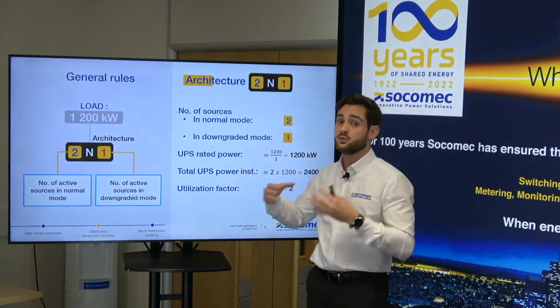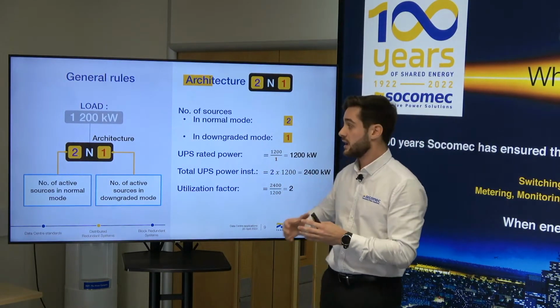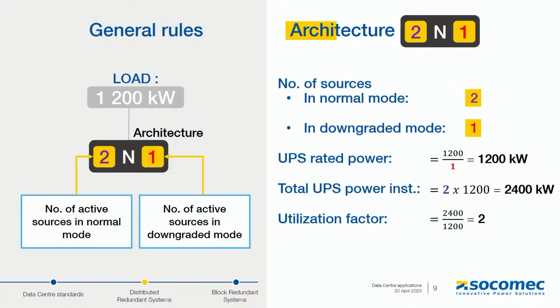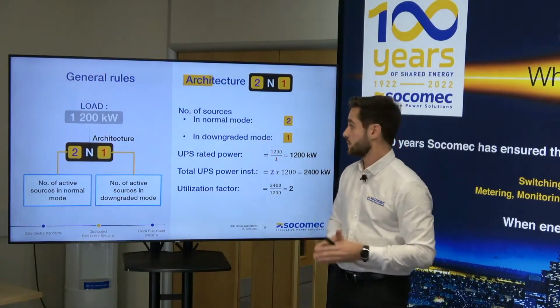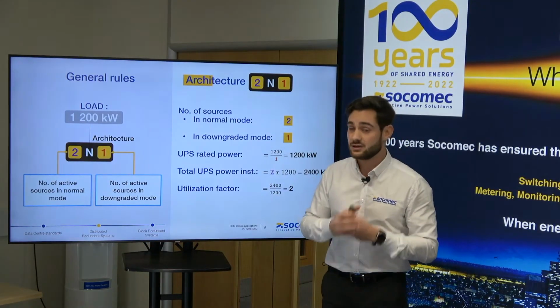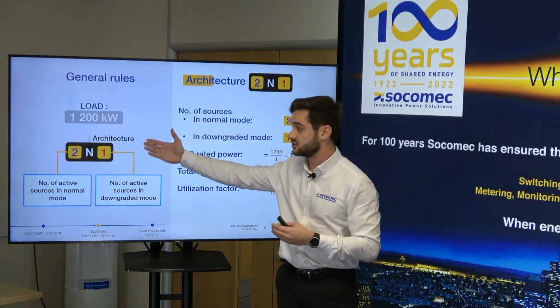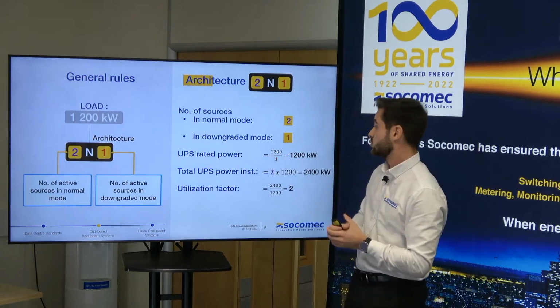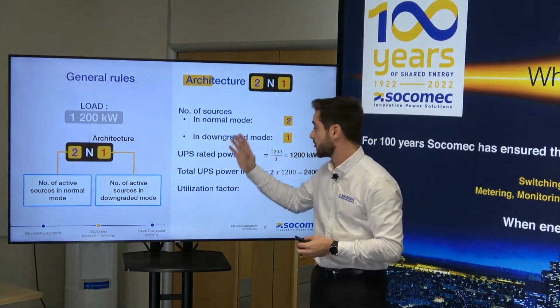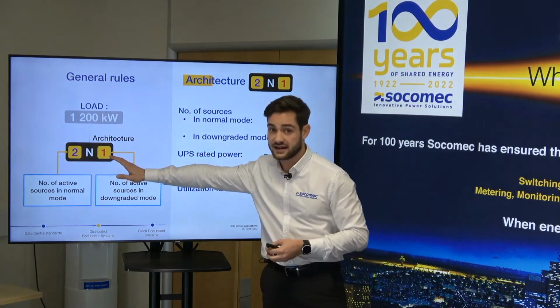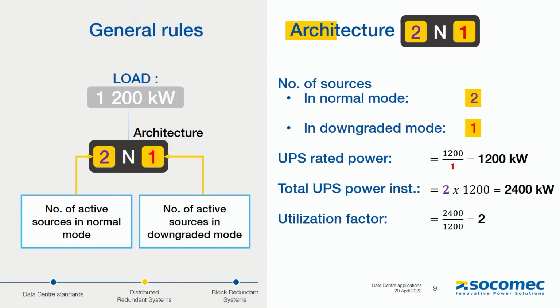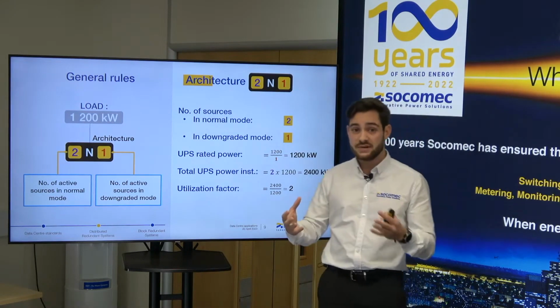So the one we've just seen was 2N. But when we say 2N, we can also call it 2N1. So 2 represents the number of active sources for the load in normal mode. And then in downgraded mode, if there is a failure on one source, that's the one we will be relying on. So let's take the example of a load of 1200 kilowatts. How do we size a system based on this load for a 2N1 application? We take this load of 1200 kilowatts and divide it by the downgraded mode, so divided by 1 in that case. We get 1200 kilowatts, which is the UPS rated power. And then we multiply this by the number of systems in normal mode, so in that case, 2 systems. We end up with a total of 2400 kilowatts, which is really a big system for this kind of load.